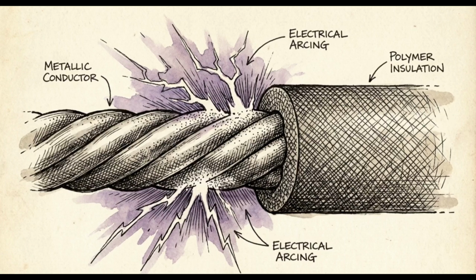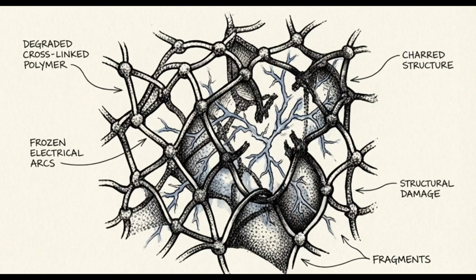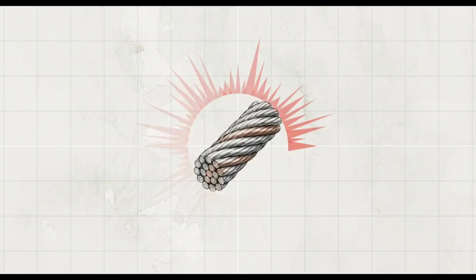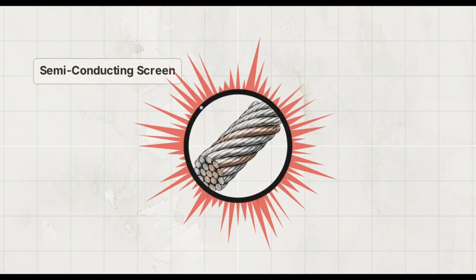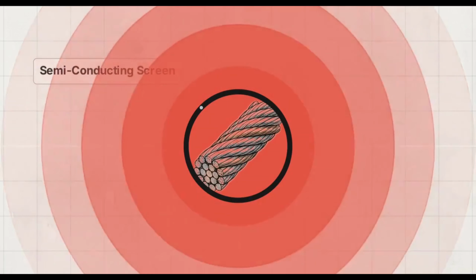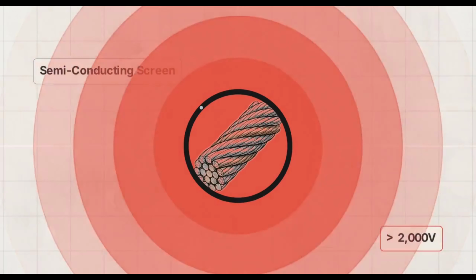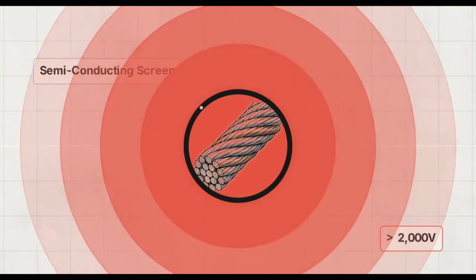In cables operating above 2,000 volts, the primary engineering concern is the management of internal electric field stress. Microscopic variations in the electric field can ionize the surrounding air, creating corona discharges that degrade the polymer insulation from the inside out. To prevent this, extruded semiconducting screens are applied over the core. These screens ensure a uniform electric field gradient, preventing localized discharges and extending the life of the asset. Managing thermal limits and controlling invisible electric field stress is what ultimately guarantees the cable's operational lifespan in a volatile grid.